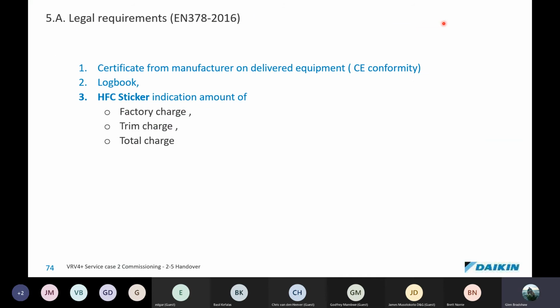The unit should have the HFC sticker indicating the amount, the factory charge, the trim charge, and the total charge, on every installation. This should also be placed in a position where it doesn't get damaged by the sun. We see a lot of stickers added to units, and within a couple of months, because of the sun, you can't read them any longer. So we recommend that when we add these stickers, we write in the amount of refrigerant, and put it in an area where it cannot be rubbed away.